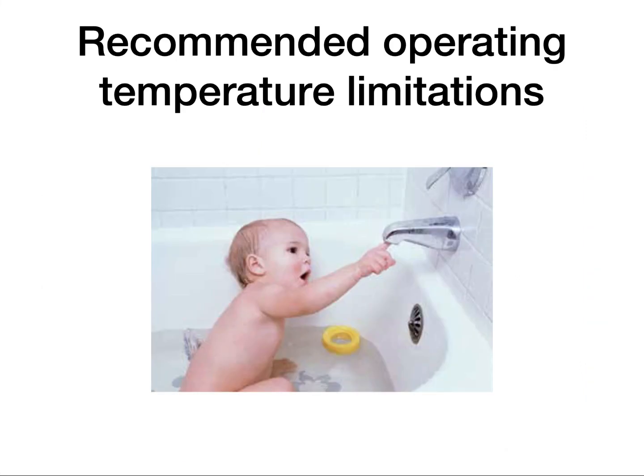The recommended operating temperature limitations are generally dictated by the authority having jurisdiction. In this case, it's dictated by the Denver Health Department. Their minimum recommended water operating temperature is 120 degrees Fahrenheit to the furthest point of use, and it must be readily available within 10 seconds of having opened the tap.